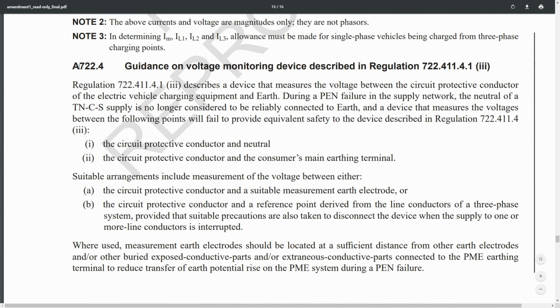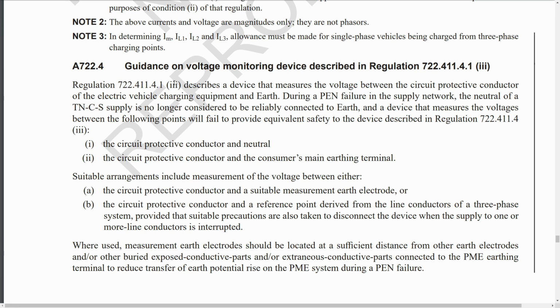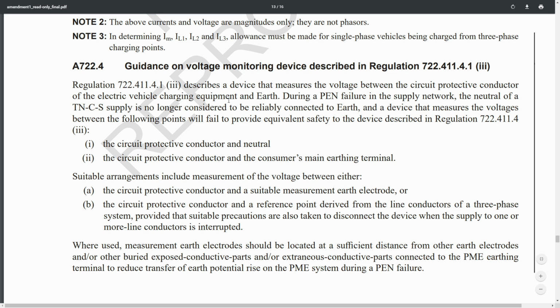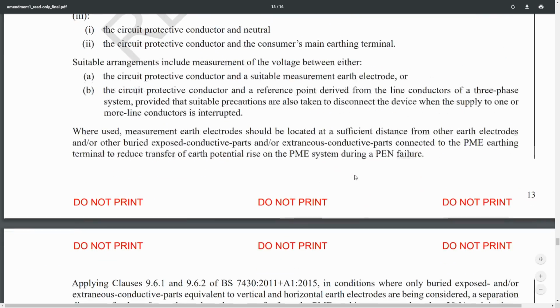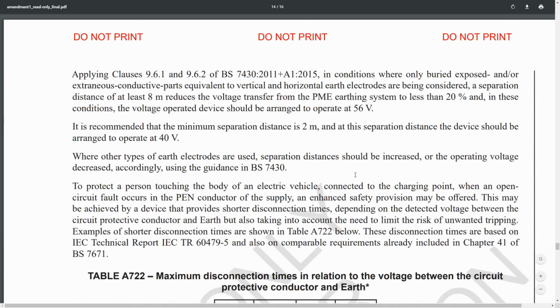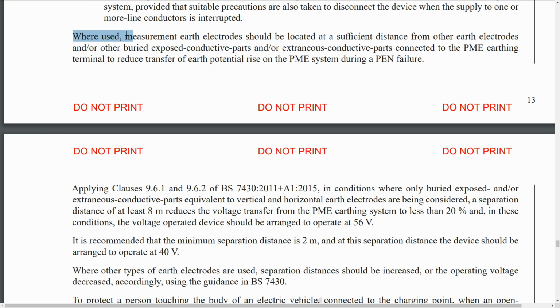This used to be a section here on symbols used, so they've added this piece in on voltage monitoring device, and this again refers to this unicorn device which doesn't exist, so it's monitoring the voltage between the circuit protective conductor and the earth itself, meaning there's got to be a reference earth electrode. Bit of information about there how it could actually work, but again this doesn't exist, so until it does, not a whole lot of point in going in there. We've got an interesting bit here about where used.